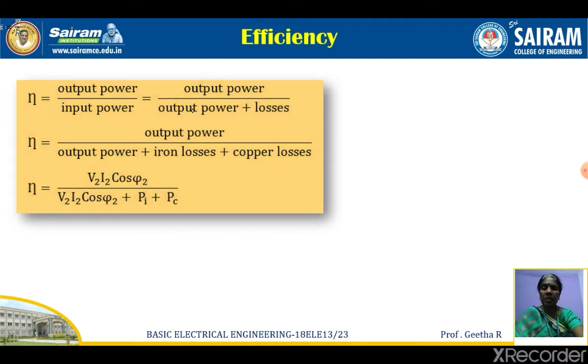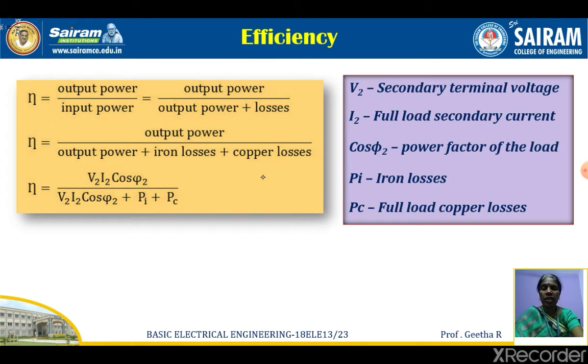The input power can be written as the output power plus losses. So the efficiency can be written as output power divided by output power plus the losses. Again it consists of two losses, that is iron losses and copper losses. So you can substitute for the output power, that is V2 I2 cos phi 2, for the iron loss it is Pi, and for the copper loss it is Pc, where V2 is the secondary terminal voltage, I2 is the full load secondary current, cos phi 2 is the power factor of the load, Pi is the iron loss, and Pc is the full load copper loss.